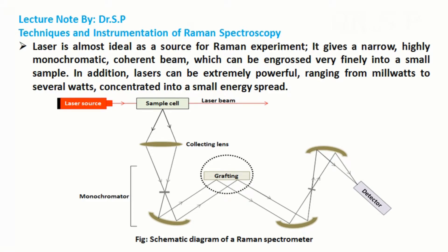In this tutorial we will discuss techniques and instrumentation of Raman spectroscopy. A laser is almost ideal as a source for a Raman experiment — it gives a narrow, highly monochromatic, coherent beam, which can be focused very finely into a small sample.